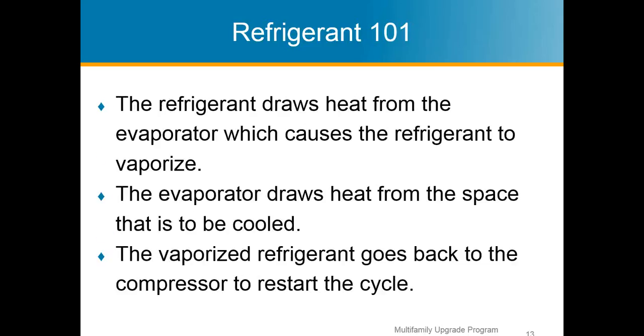So again, the refrigerant draws the heat from the evaporator, which causes the refrigerant to vaporize. The evaporator draws the heat from the space to be cooled, so what you're left with is cool air that goes back to the space, and it's just a constant cycle. What the VRF system is trying to do, and it does, is take that unwanted heat and, through the refrigerant lines, transfer that heat energy to another space that is calling for heating. It's a very sophisticated system, and you're seeing them more and more prevalent in the market.